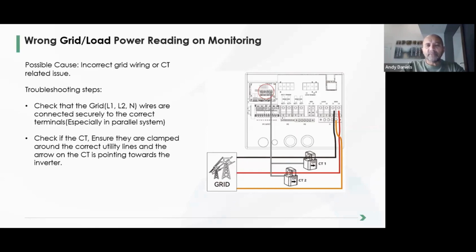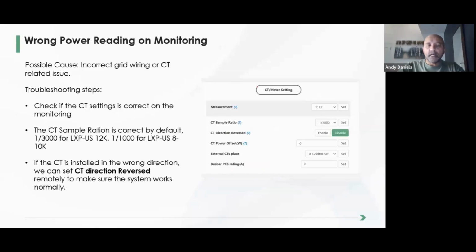What happens if you have one of your technicians, they do an installation, and the panel is quite cluttered with wires, and he's really got to get his hand in there and find the hot, and he gets it clamped on, he clamps the other one on, and he inadvertently clamps the CTs on in the wrong direction? Does he have to go back in there and turn them around?